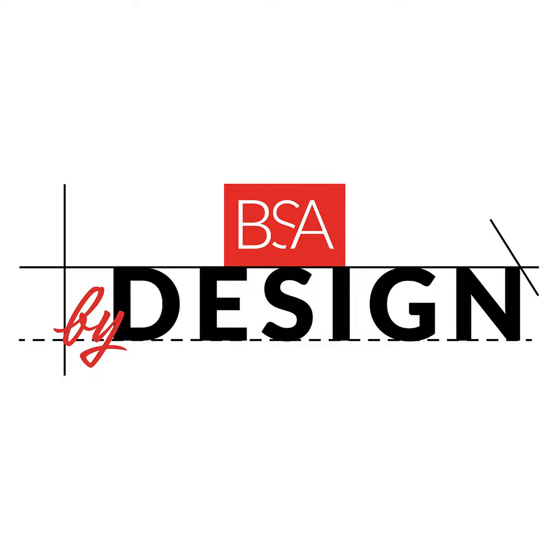We started getting into talking with some of these newer controls companies that are going to start integrating AI into the algorithms on when the decision is made to do X, Y, or Z, using historical data as well as trending data in the hospital it's being used in to find the most efficient way to have everything operate at the least kW per ton possible.